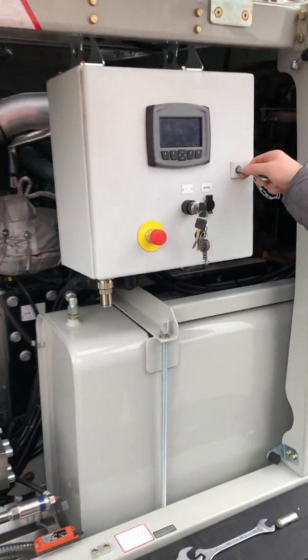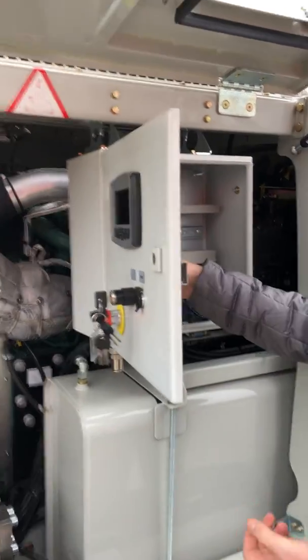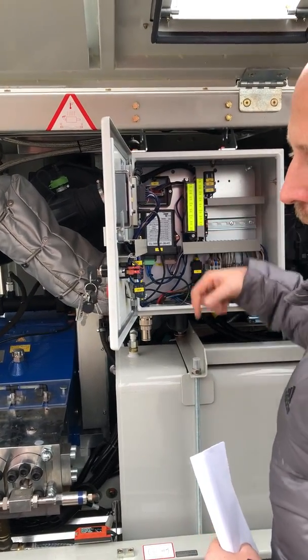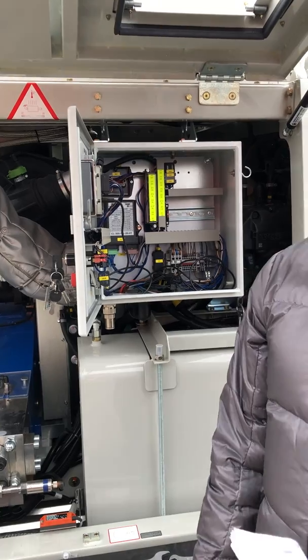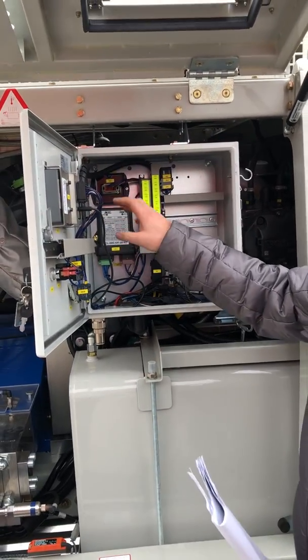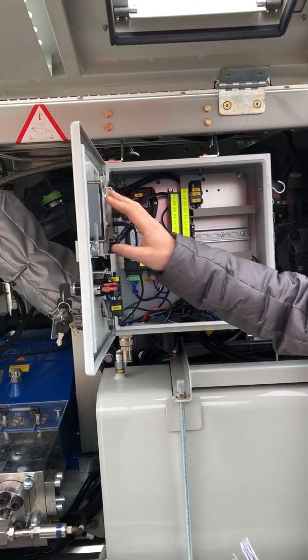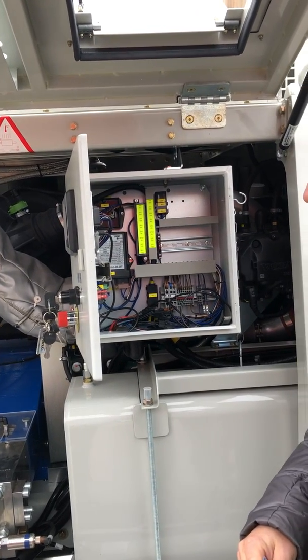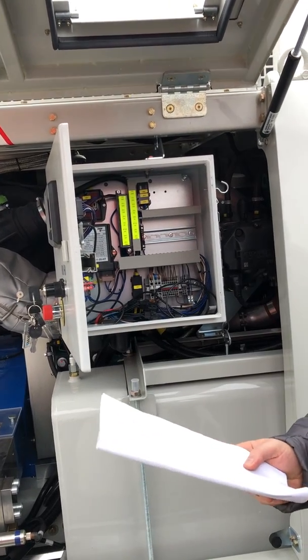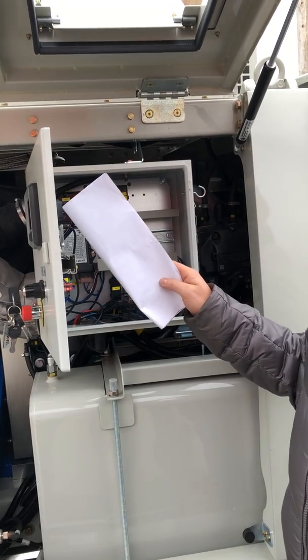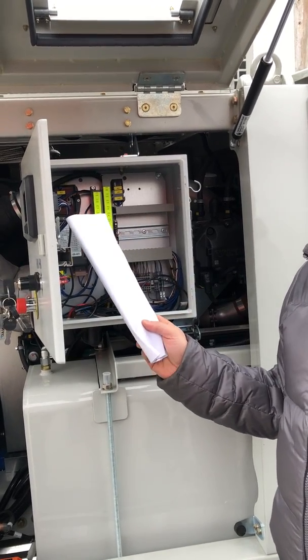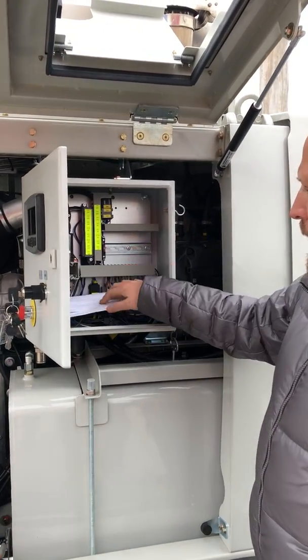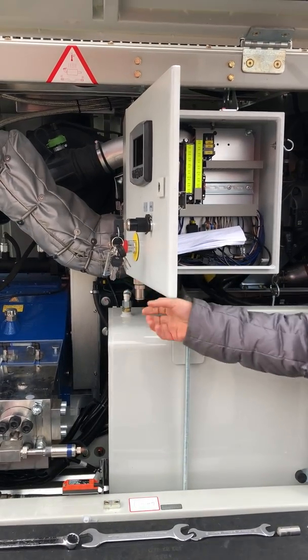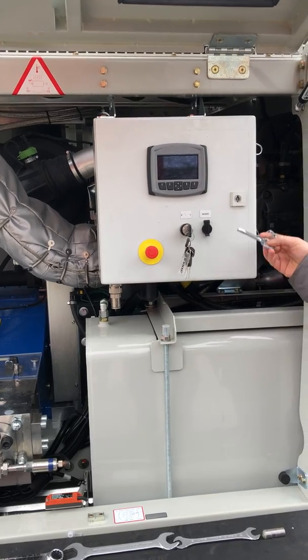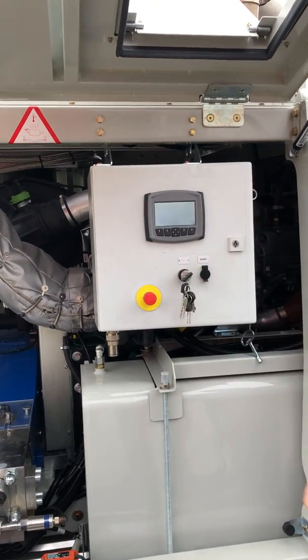If you look inside the control box, there's not much in there. Only one relay. This relay switches on and off the electric water pump. Everything else is controlled. This display is a controller. Those two are input-output modules, and the big one also has a controller in there. So all the safety functions are calculated by both units and then compared. This way we get safety because we have two units that compare what they calculate. This is the connection port for the external e-stop, and so a very simple electric box.